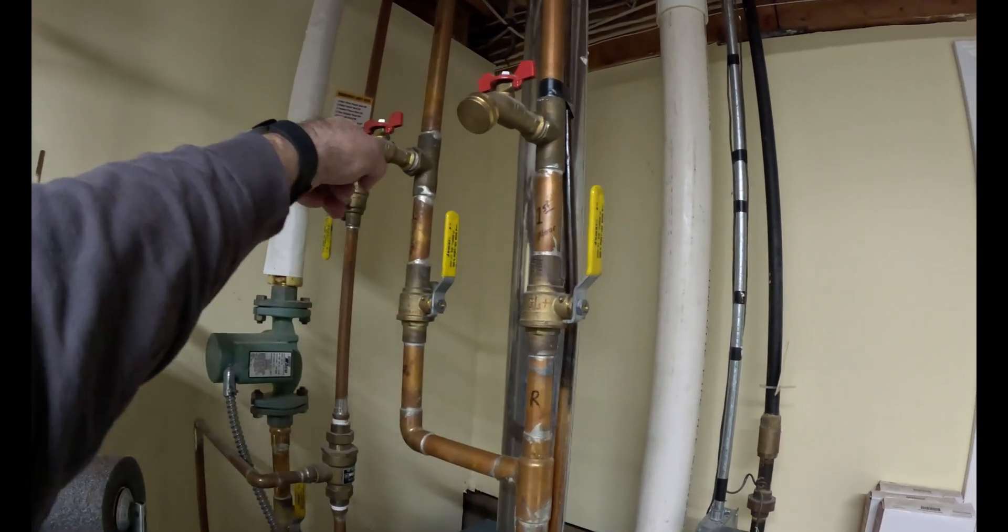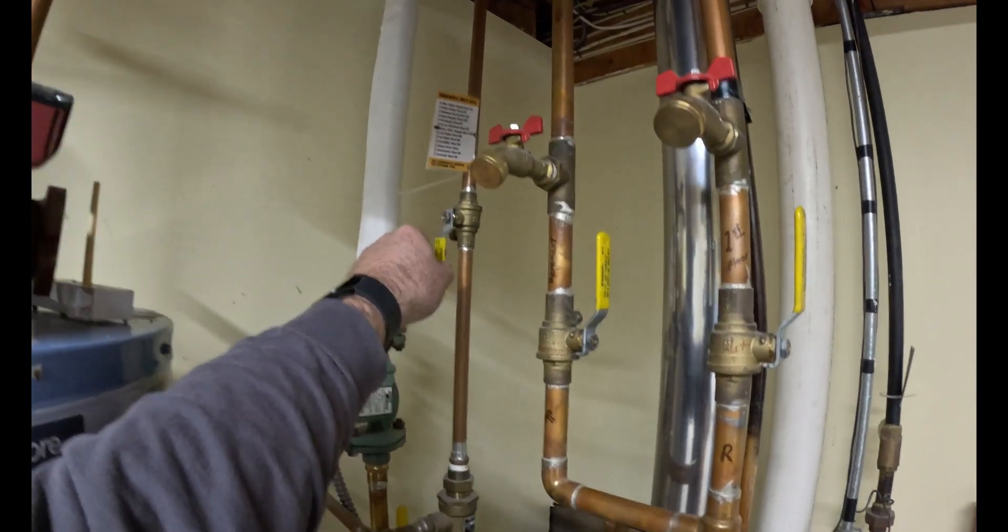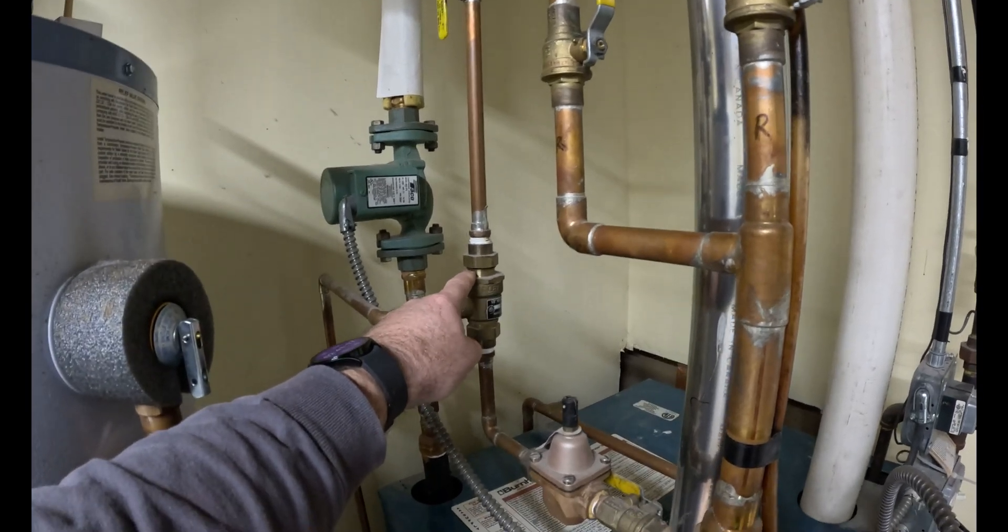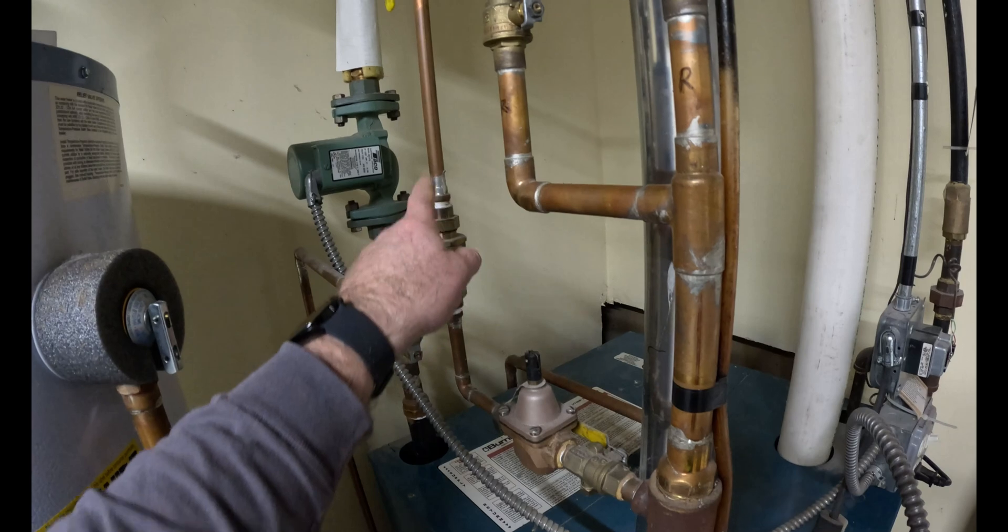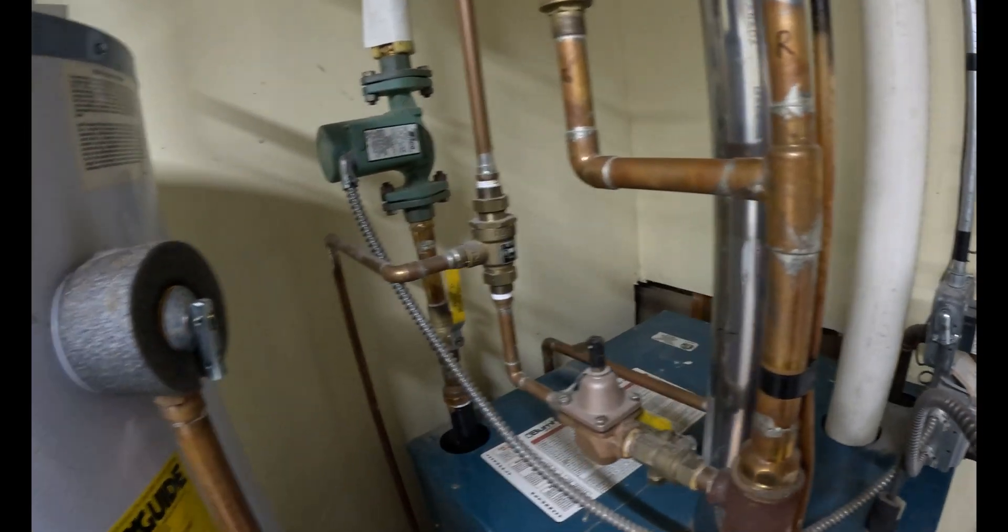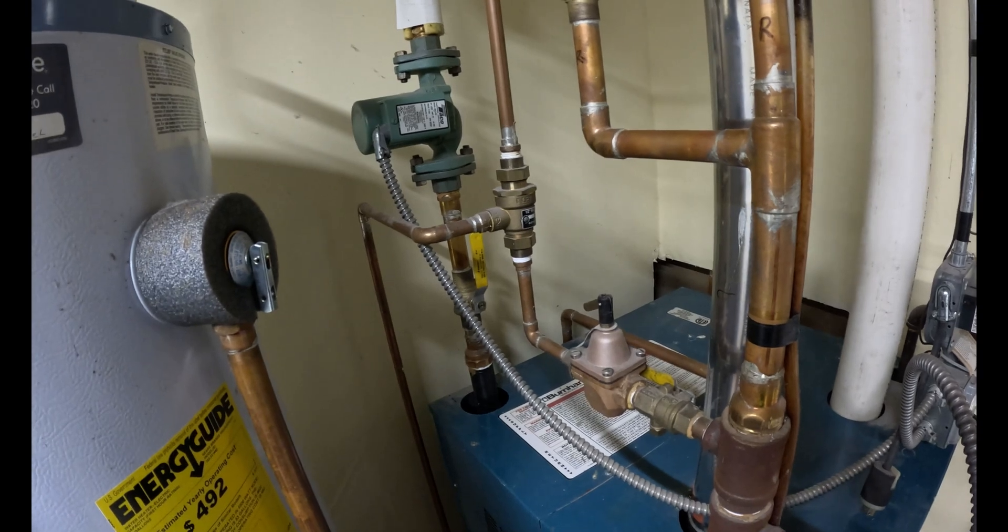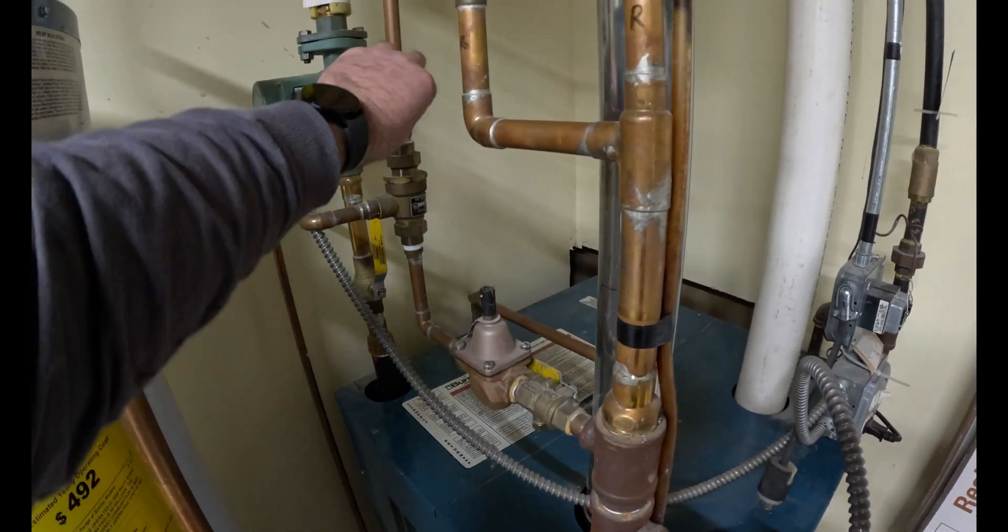This here is your water feed into the boiler, half inch copper into our backflow preventer, which keeps the boiler water separate from the house water. So if there was ever a fire on the street or some major plumbing done, this keeps the water inside the boiler and this keeps the house water inside the house water, keeps everything separate.